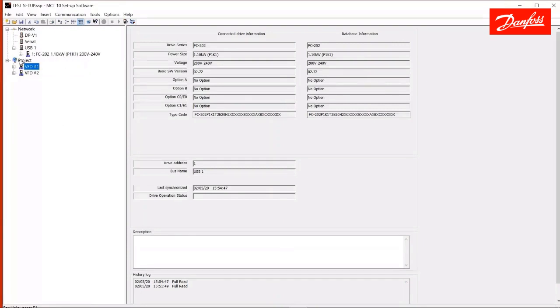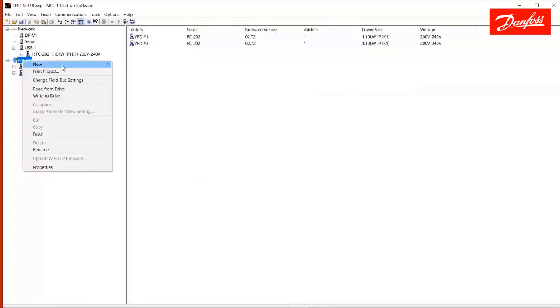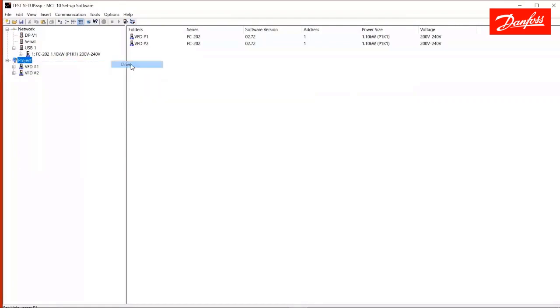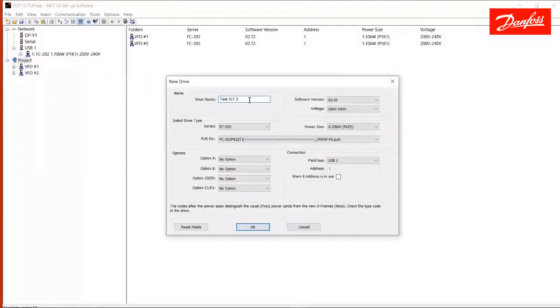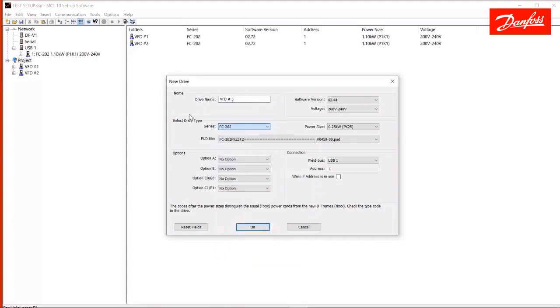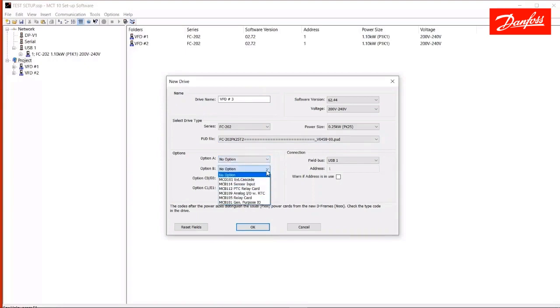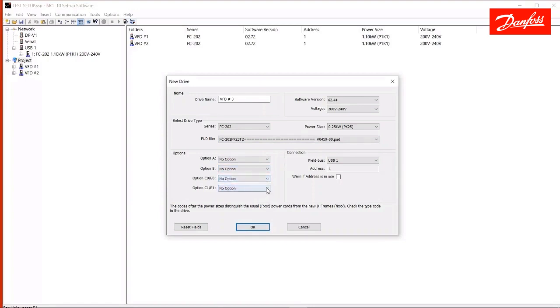So, another thing you can do on the project side is create a generic drive. So, I'm going to right click here and select new drive. I'm going to choose the type. We'll call it test drive or VFD number three. You select the series of interest. So, we'll pick an FC-202 AquaDrive here. If there are any option cards on the drive, including serial communication option cards, general purpose IO option cards, or C options, which are motion control option boards, I would select them here in the menu so that the software understands and includes those parameters.